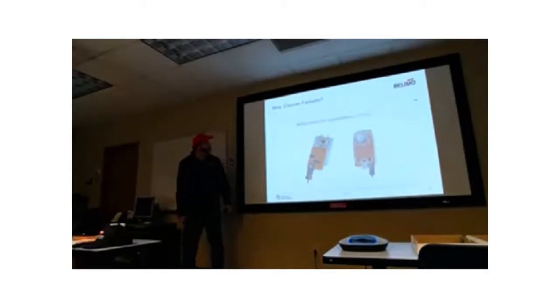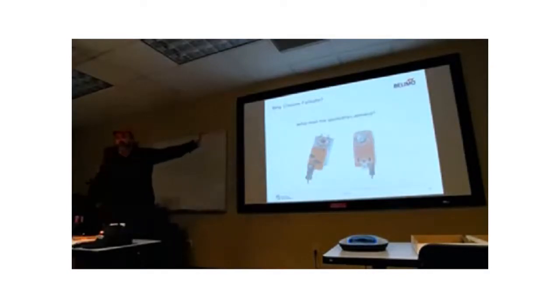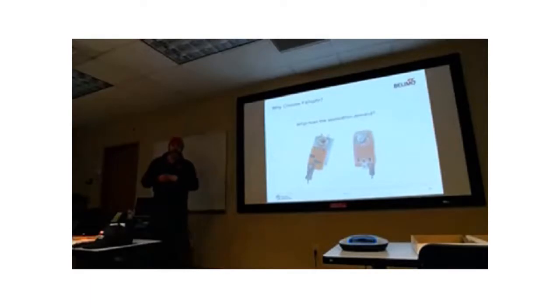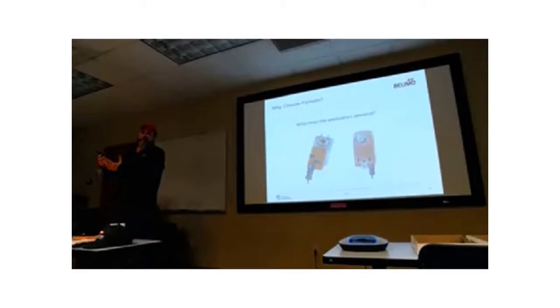All right. So failsafe, everybody's clear on why we use failsafe, right? Or is anybody not clear? Why do we use failsafe actuation? Anybody know? What's that? Power loss. Well, yeah, somebody has decided that when the power goes out, I want this valve or actuator to do something that makes me fail safe, right? Like a really good example would be a steam valve, right? If you lose your power to a steam valve that actuates it, what do you think you want it to do? You want it to go closed, right? In almost all cases, you want that valve to go closed.